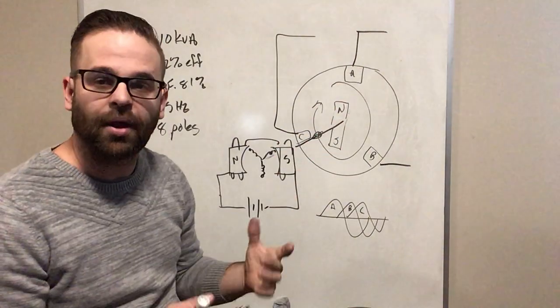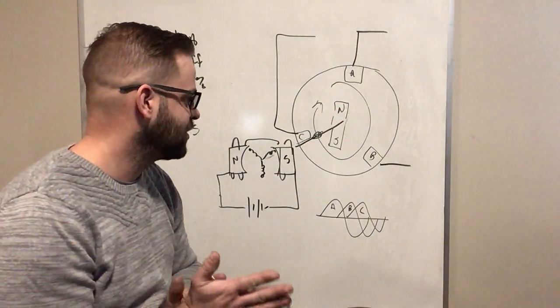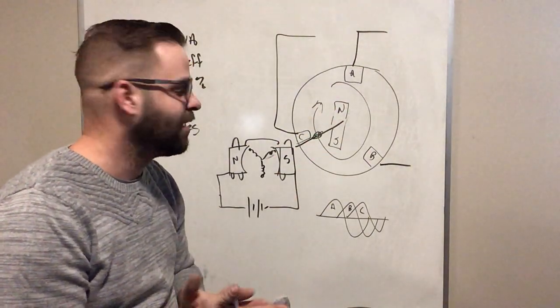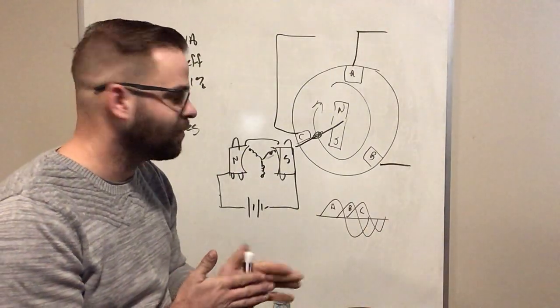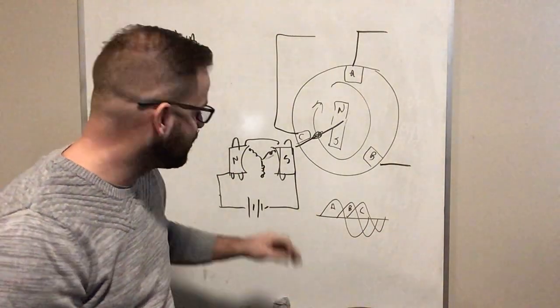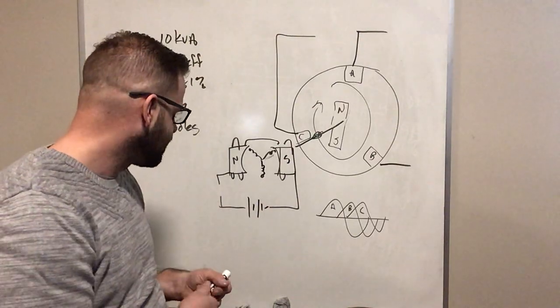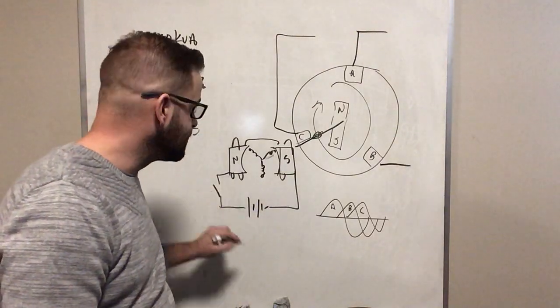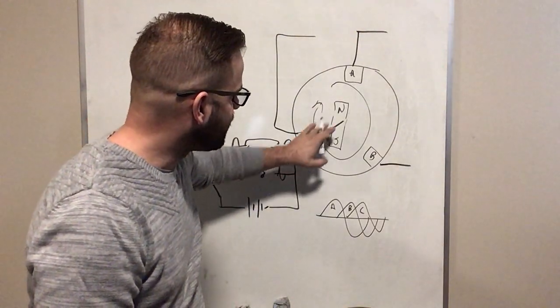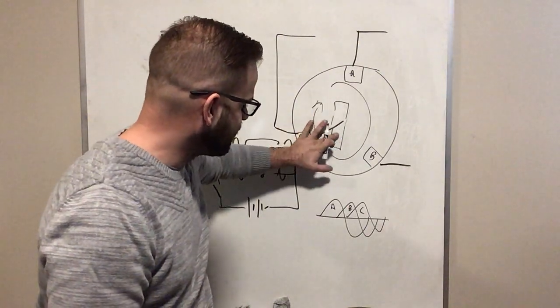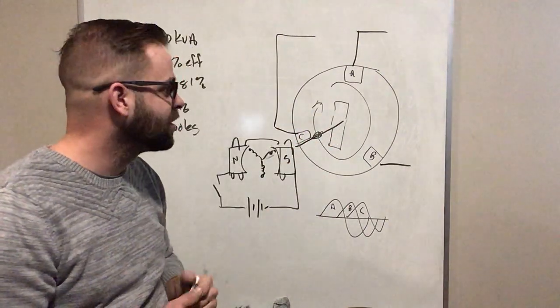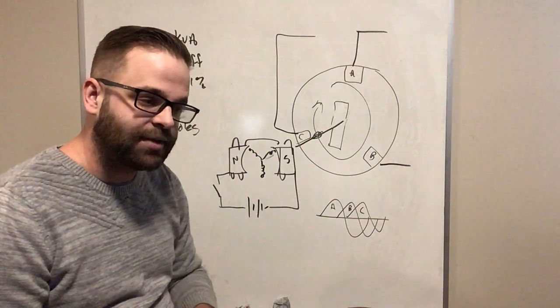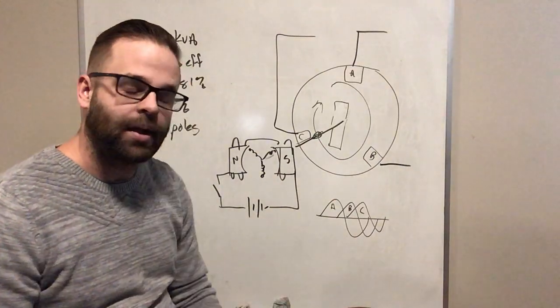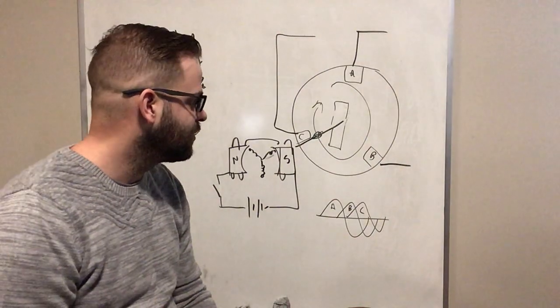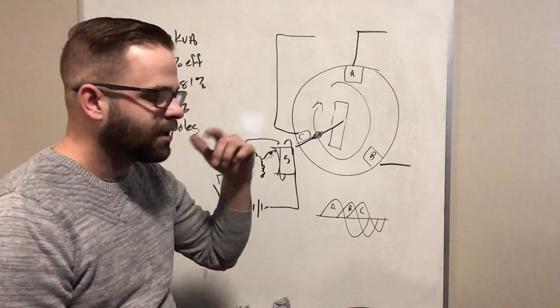So I'd end up getting a locked rotor in the center of that machine. And I would have a huge amount of current going through that, which would damage a lot of stuff. So I always want to make sure on startup that my DC excitation is de-energized, so I don't have a magnet. So on startup, I just want to leave that DC excitation off. I want to turn power on to that machine so that I can get a rotating magnetic field.